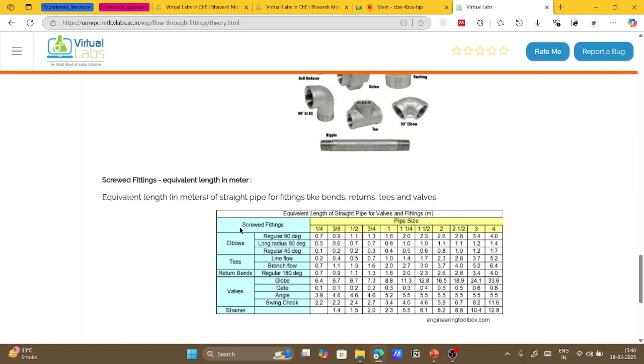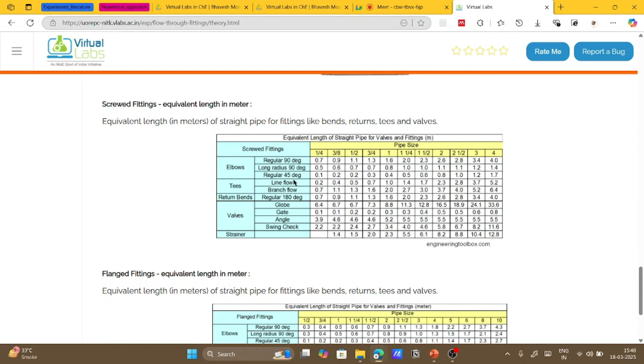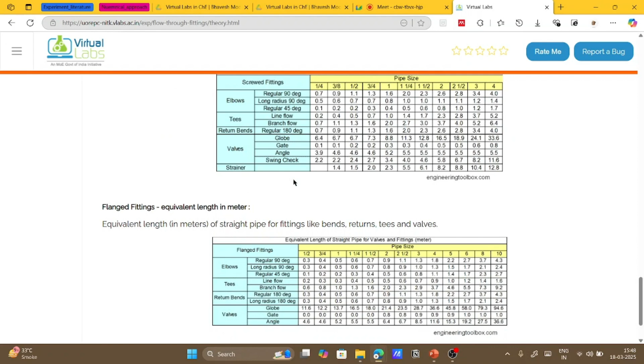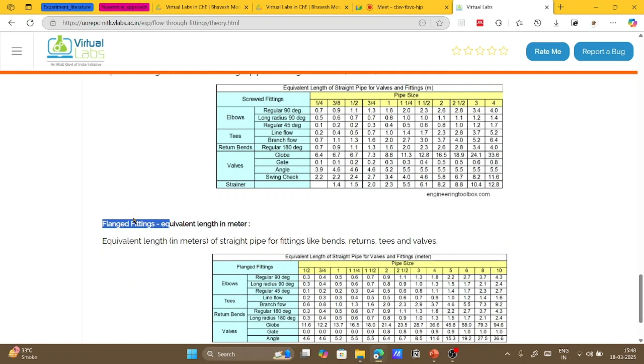The theoretical part we understood is provided here, and you can see here also the equivalent length values, or K values, that will be provided. So a reference value is given here for different valves, for different pipe sizes, what will be the L equivalent, right? You can see this is for screwed fittings and flanged fittings. There are different values for both of them. Similarly, if it's welded then there will be a different value.